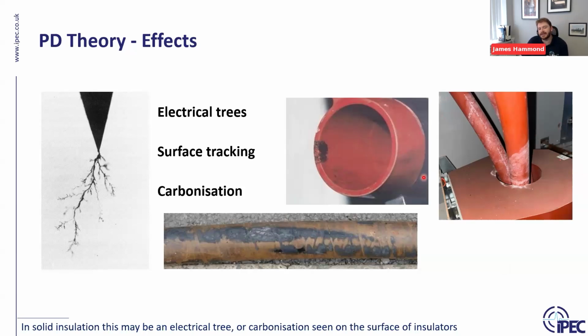What's happening is you get a breakdown of the nitrogen in the air that forms a precipitate on the surface of the insulator. And this is bad for two reasons. One, you've got a corrosive acid, basically, on the surface. Two, you've got evidence of PD. And then, thirdly, this is actually an accelerant. It creates an area of a different medium, generally more conductive than the insulator, which can then promote or exponentially increase those PD pulses.